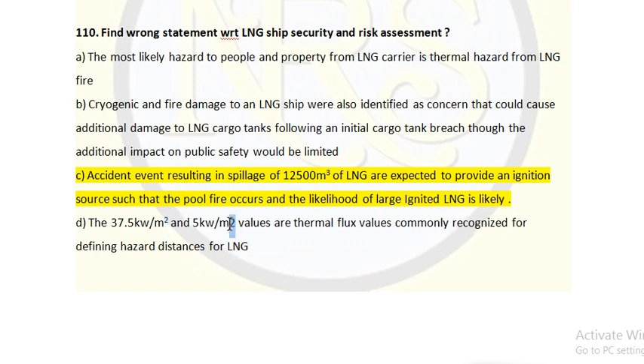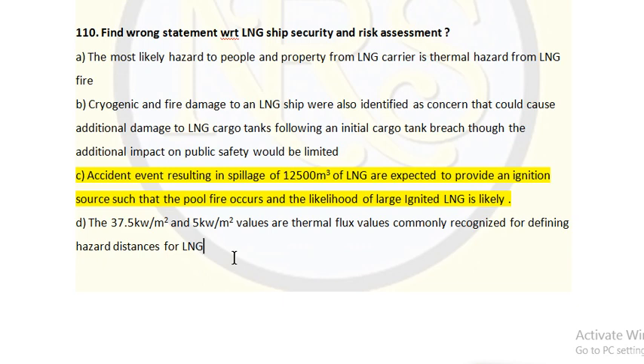The correct answer is option C. An accident event resulting in spillage of 12,500 cubic meters of LNG is expected to provide an ignition source such that a pool fire occurs and the likelihood of large ignited LNG is likely - this is incorrect because it's not about the quantity. Whatever LNG is released, it will not immediately catch fire, because its flammability range is 5 to 15%. When it contacts the atmosphere, it gets enriched beyond 15%, so it won't reach above the LFL and won't catch fire. Only once the cloud disperses and moves away, within that long process, if an ignition source meets it while it's within the 5 to 15% flammable range, will it ignite.